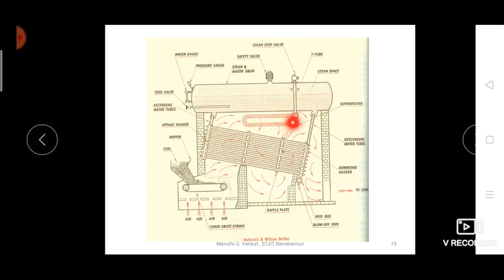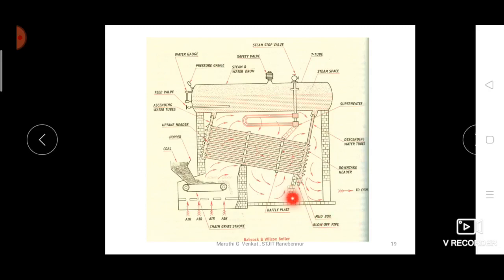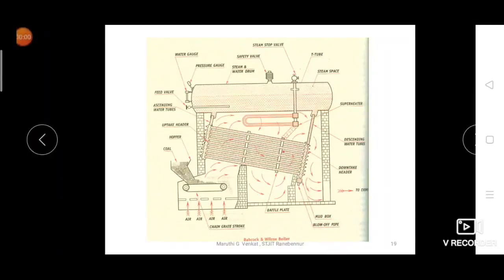The superheater tubes convert saturated steam into superheated steam. The baffle plates guide the hot flue gases to move over the inclined water tubes. There is a mud box to collect mud particles, and a blowoff valve to remove ash particles, mud particles, and excess water from the boiler.